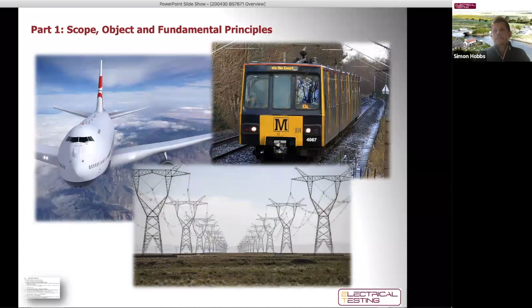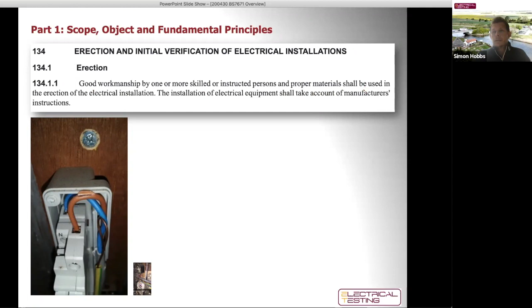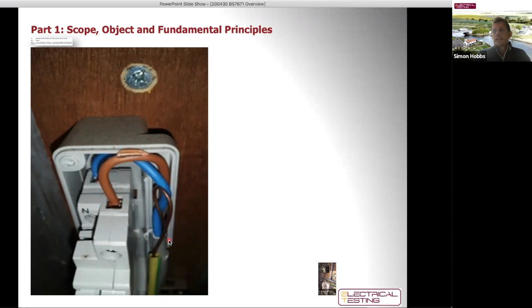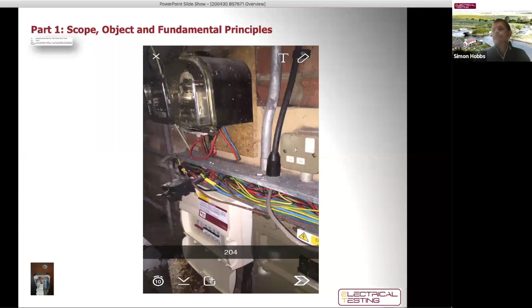Moving on through part 1, the last thing I'd like to touch on here is probably my favourite regulation, 134: good workmanship by one or more skilled or instructed persons, and proper materials, shall be used in the erection of the electrical installation. If you comply with that regulation, these sorts of issues don't occur, because things would have been installed correctly - we won't have cable damage, we won't have unsleeved protective conductors, and we won't have new trunking installed with new conduit and all the cabling jammed in to the point where the lid won't fit. Just by following almost the first regulation in the whole standard, we can cover off a lot of what we later check through inspection and testing.